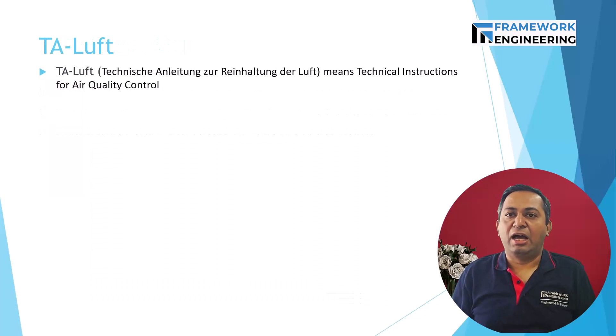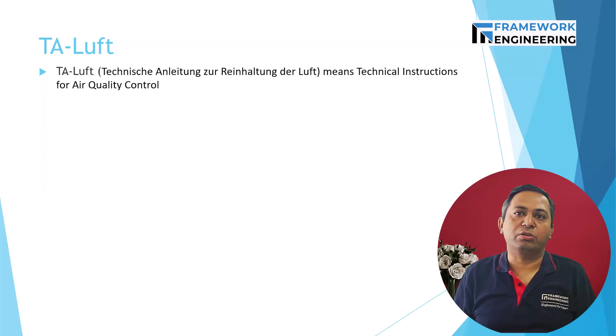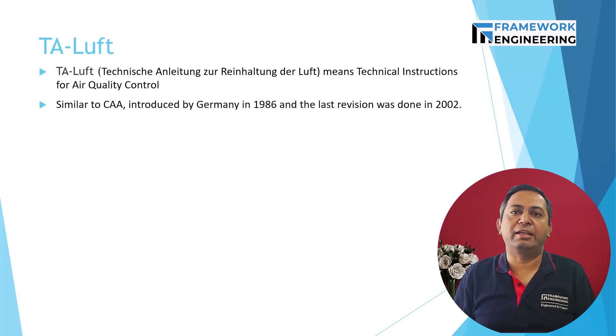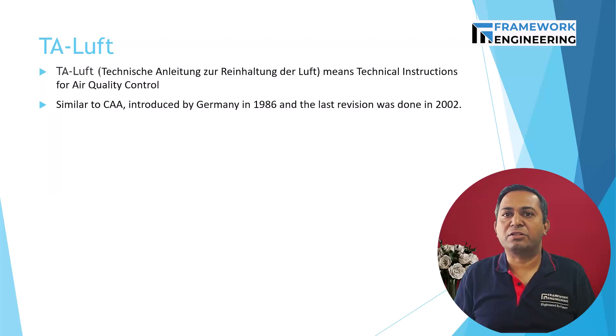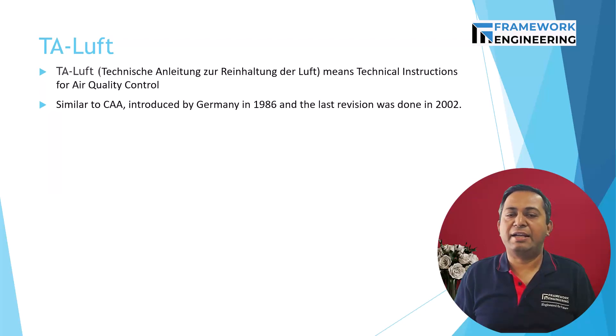Similarly, TA-Luft — which means Technical Instructions on Air Quality Control — was introduced by Germany in 1986, with several updates up to 2002, so the latest version is from 2002. There is a test done by a different standard, VDI 2440, where the acceptable leakage rate is 10 raised to minus 4 millibar·litre per second for temperatures up to 250 degrees centigrade.